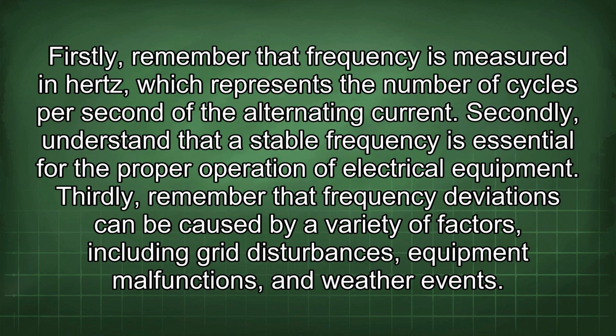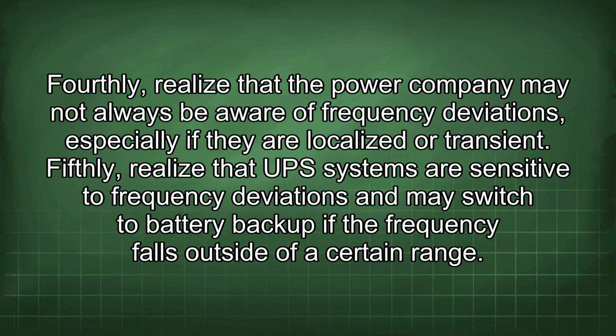Firstly, remember that frequency is measured in hertz, which represents the number of cycles per second of the alternating current. Secondly, understand that a stable frequency is essential for the proper operation of electrical equipment. Thirdly, remember that frequency deviations can be caused by a variety of factors, including grid disturbances, equipment malfunctions, and weather events. Fourthly, realize that the power company may not always be aware of frequency deviations, especially if they are localized or transient. Fifthly, realize that UPS systems are sensitive to frequency deviations and may switch to battery backup if the frequency falls outside of a certain range.